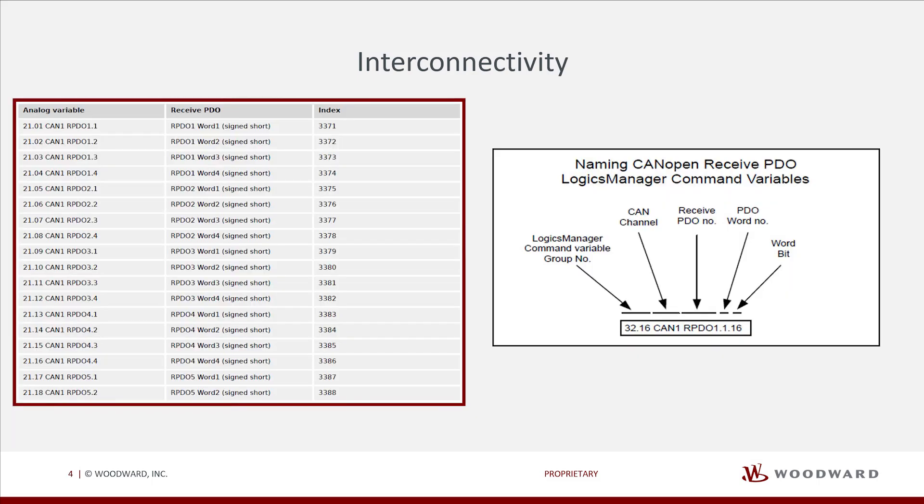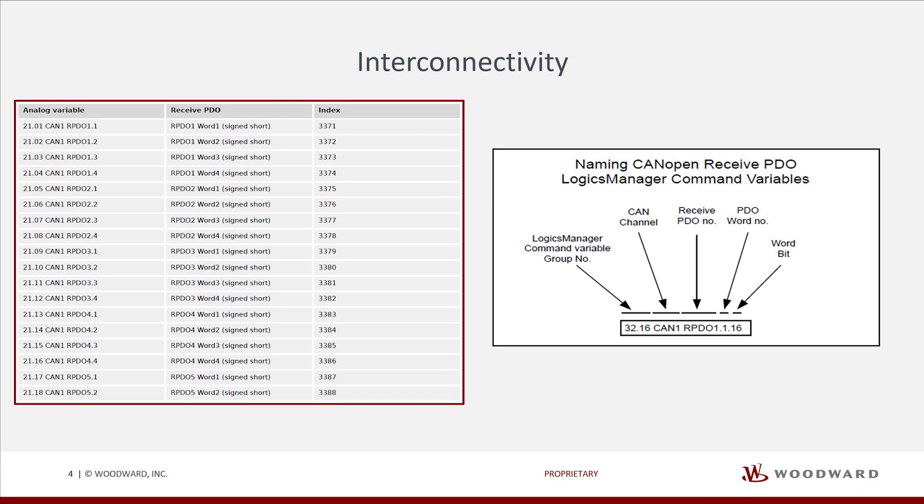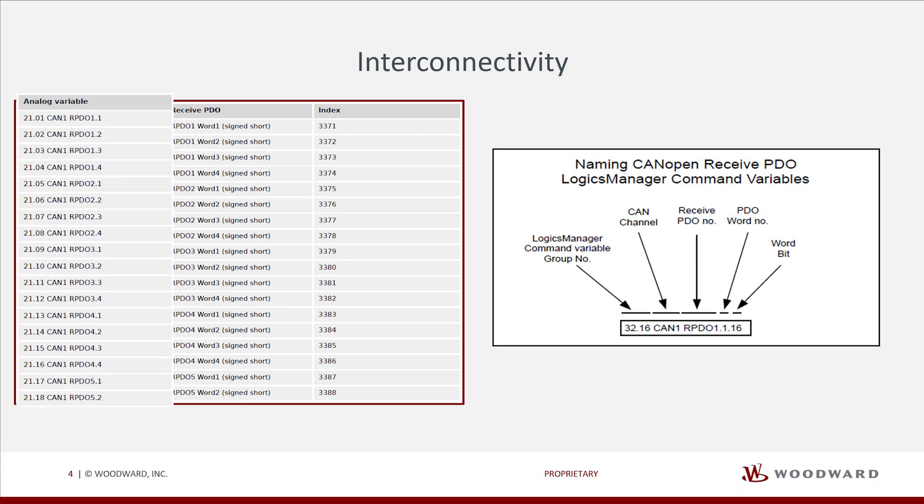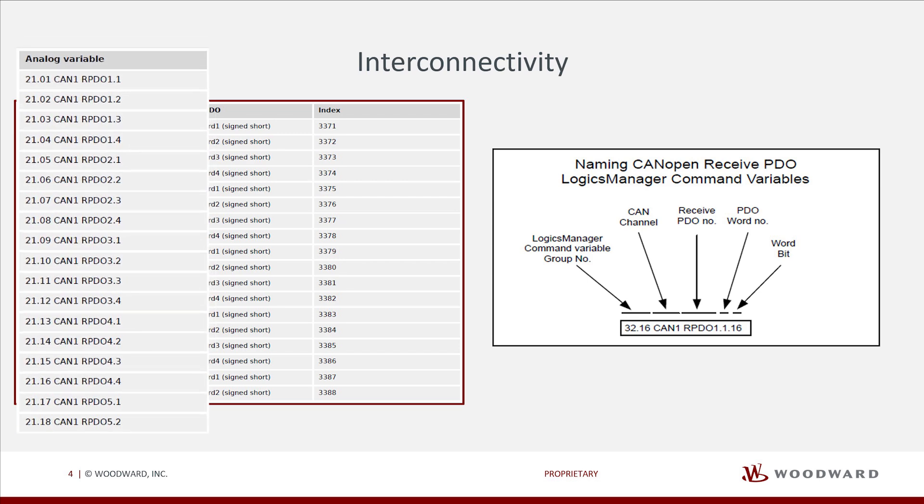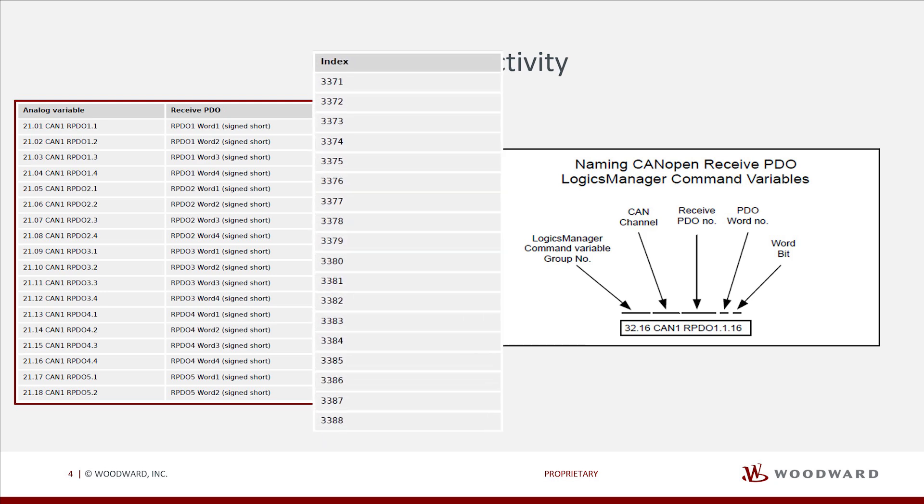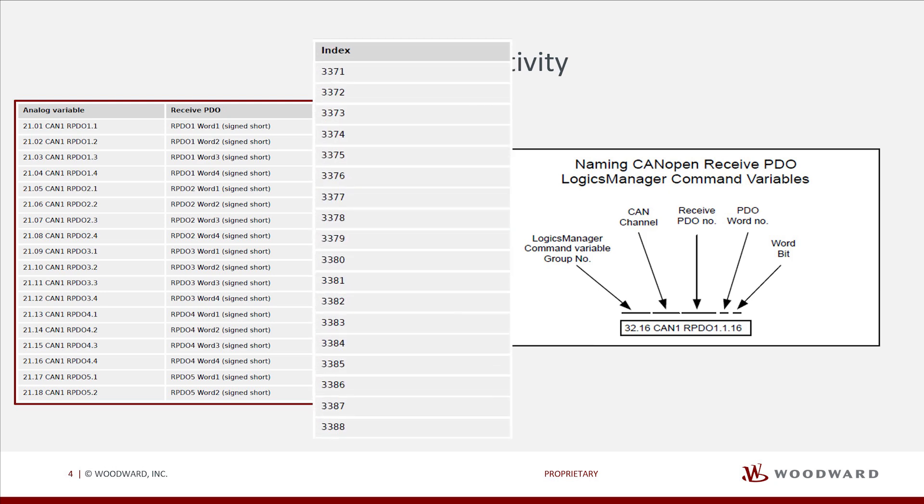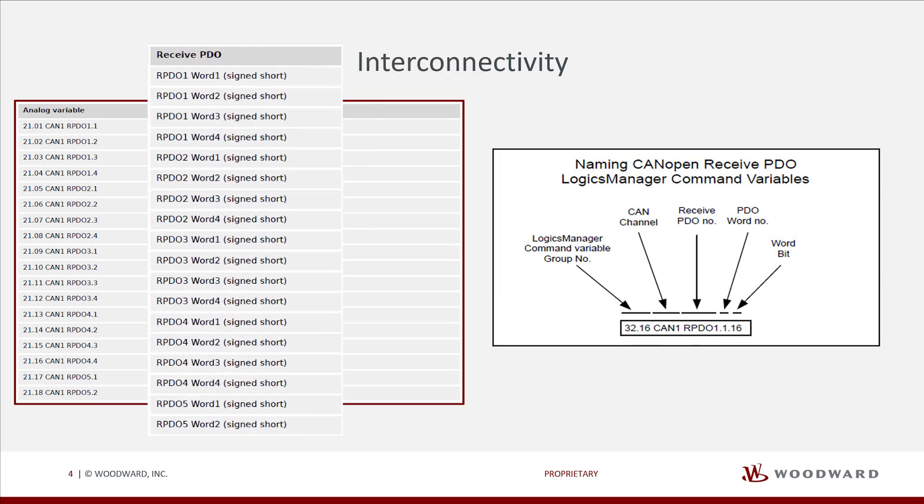The table here shows data which can be received via CAN RPDO from any other device. These data are available as analog variables of Group 21, and can be assigned to Analog Manager equations for example for free alarms or setpoints. For usage with CAN, the corresponding indices must be mapped to the RPDOs.